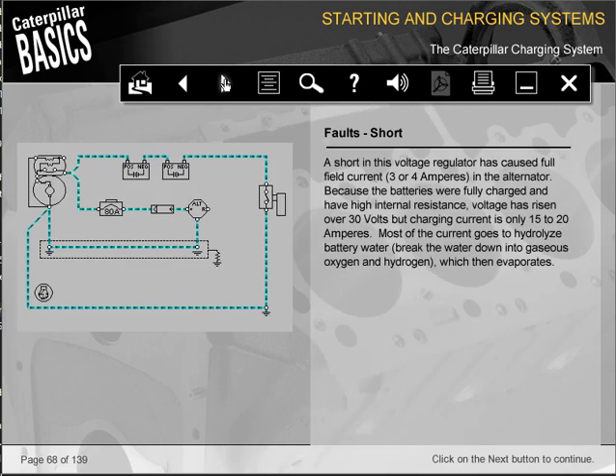A short in this voltage regulator has caused full field current, 3 or 4 amperes, in the alternator. Because the batteries were fully charged and have high internal resistance, voltage has risen over 30 volts, but charging current is only 15 to 20 amperes. Most of the current goes to hydrolyze battery water, break the water down into gaseous oxygen and hydrogen, which then evaporates.